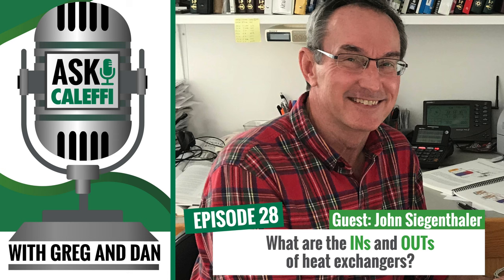Yeah, we have been asked, and I suspect you guys probably get this question too, can I use a heat exchanger in place of a hydraulic separator? Oh, yeah. We get that. Yeah, and vice versa. You can, but the heat exchanger really isn't designed for air separation or for dirt separation. So you're not getting those functions. You're going to have to add that functionality with other components. And unless there's some reason you're trying to separate the fluids on the boiler side of the system from the load side, where you want absolutely no contact between those fluids, there's really no reason to use a heat exchanger there. It probably would be more expensive than a hydraulic separator.